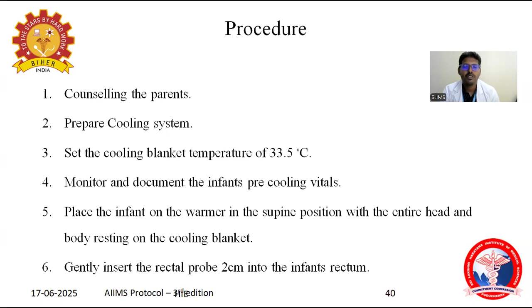After placing the child over the warmer, we should insert the rectal probe up to 2 centimeters in the infant. Once you set the target temperature at 33.5 degrees Celsius, you can keep cooling for around 72 hours, that means 3 days. Usually the secondary energy failure happens from 6 hours to 72 hours, that's why we keep cooling for around 72 hours. After crossing 72 hours, we should start rewarming. We should increase the core temperature by 0.5 degrees Celsius every hour until the child reaches 36.5 degrees Celsius.